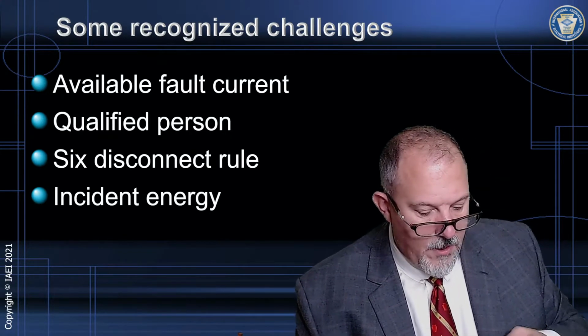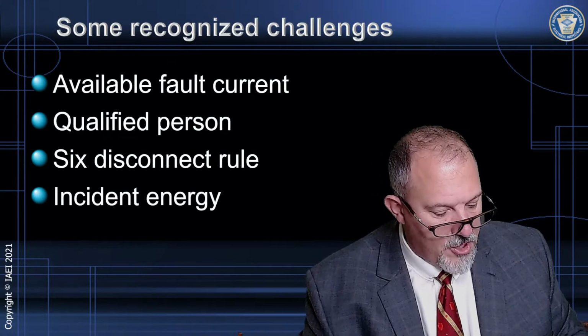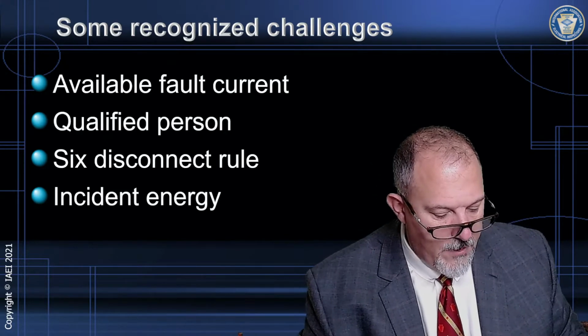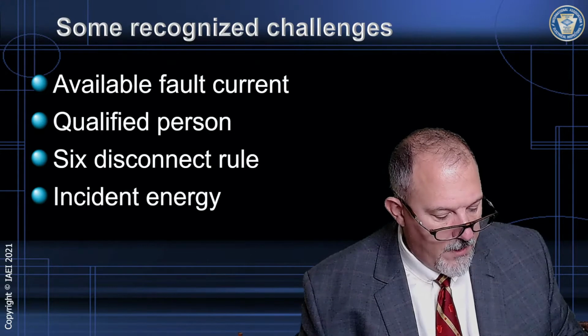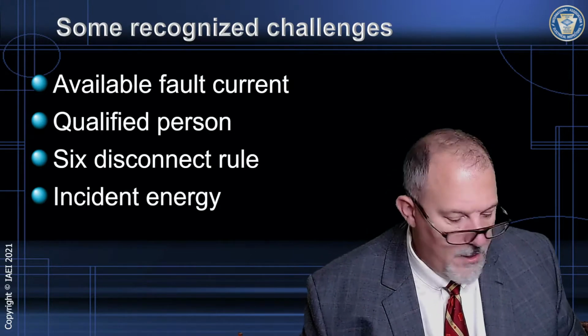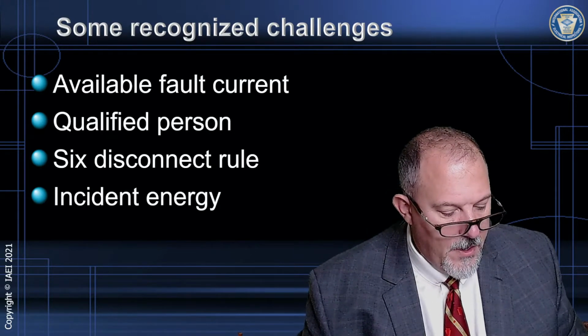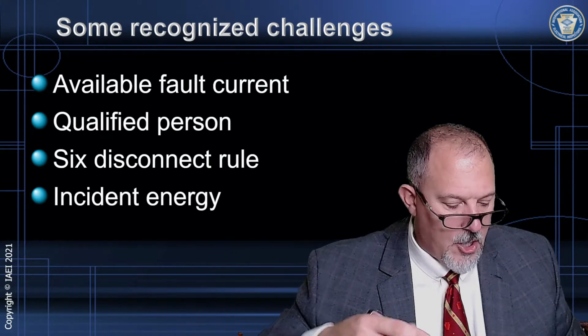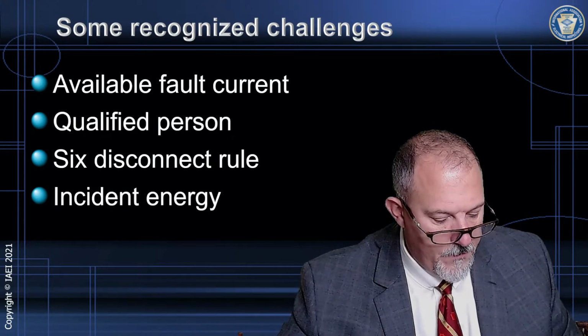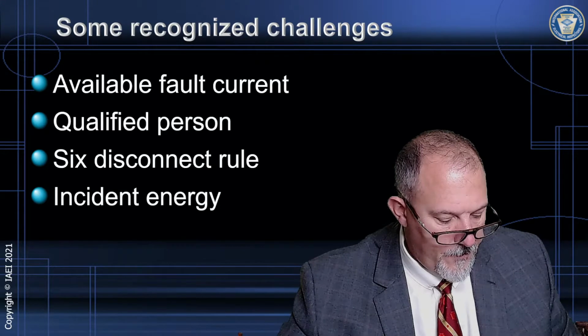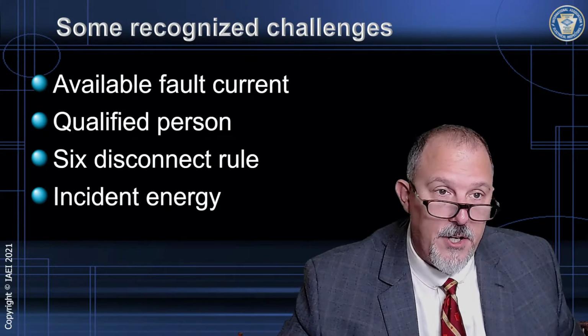Sir, and other than dwelling units, in addition, permanent labels shall be field applied for service rated 1200 amps or more, meeting the requirements of 110.16(A) and following that information. So it doesn't say a qualified person should create it. It just simply says you need to put that on.